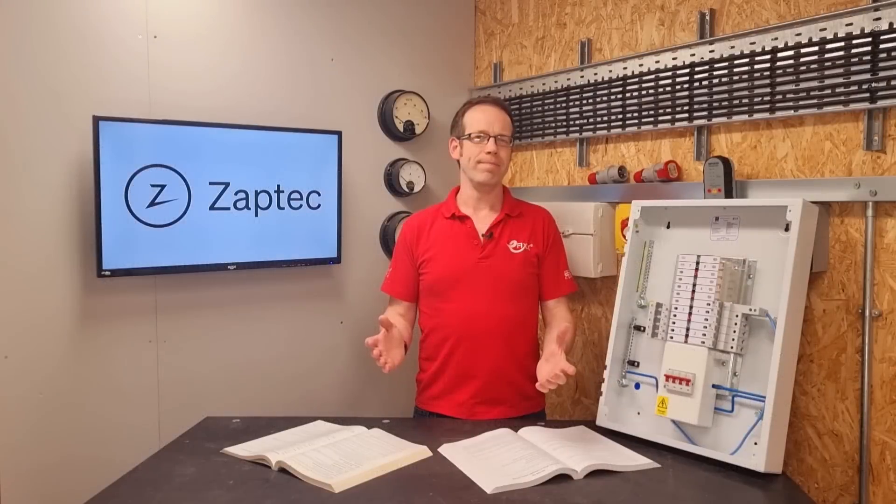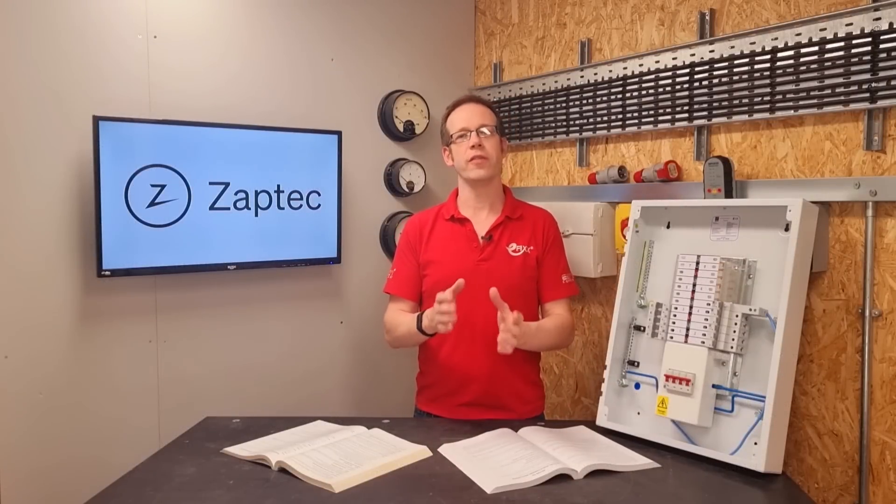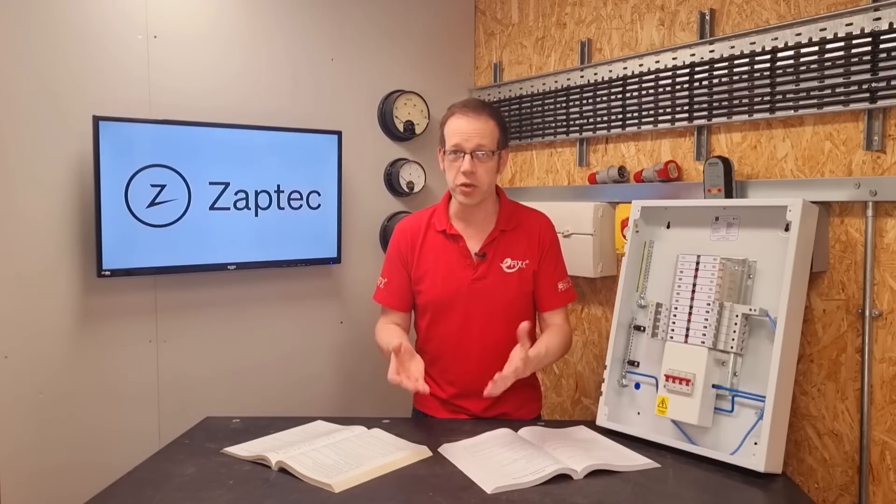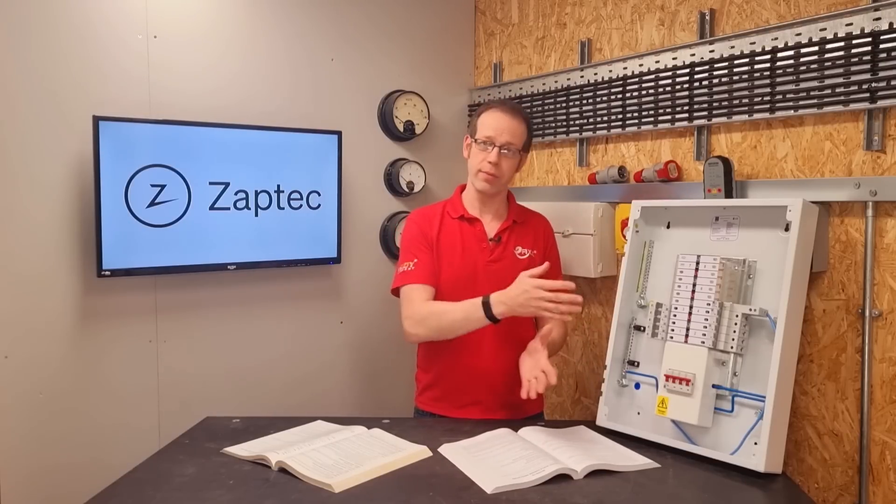So why would that happen? Well we said that in a balanced load the current trying to flow down the neutral and therefore the voltage to earth would be zero. However, the problem occurs when the loads become unbalanced and you have different amounts of current flowing through the three line conductors.